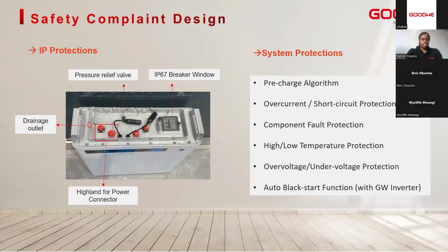Now, take an instance without the top cover. The communication cables have IP65 rated plugs, so no dust or water ingress. The breaker itself is even higher rated, IP67, no water or dust ingress to the battery itself. The power plugs are on Highland power connectors, so water levels can't really build up or rise up to seep into the power terminals. And yes, the outer surrounding area has a drainage channel and a drainage outlet to prevent any water accumulation on the top or the upper part of the battery. Now, these are very stringent measures to ensure the IP protection is up to standard and your warranty is not breached or void.